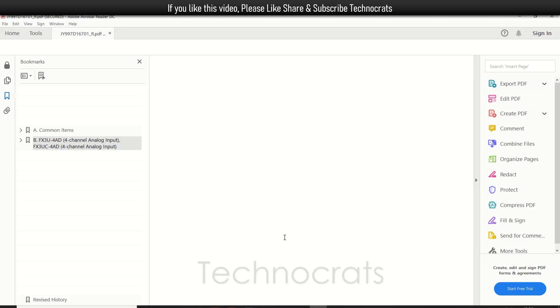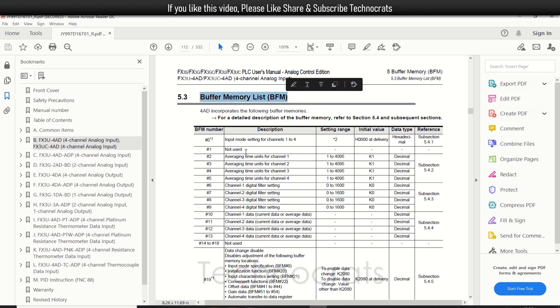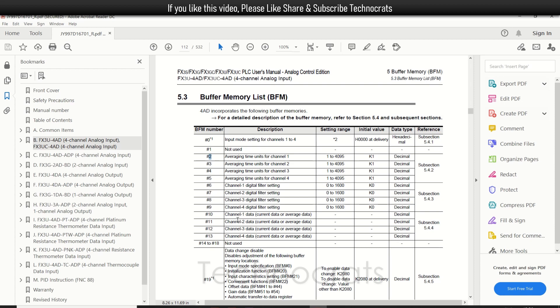First, I have opened the manual for FX3U-4AD, which is a 4-channel analog input card. As you can see, these are the buffer list of the card. Buffer number zero is for input mode selection for channels 1 to 4. Buffer 1 is not used. Buffer 2 is average time units for channel 1, and so on through channel 4. Buffers 6 to 9 are the digital filters, and buffers 10 to 13 are the input values.